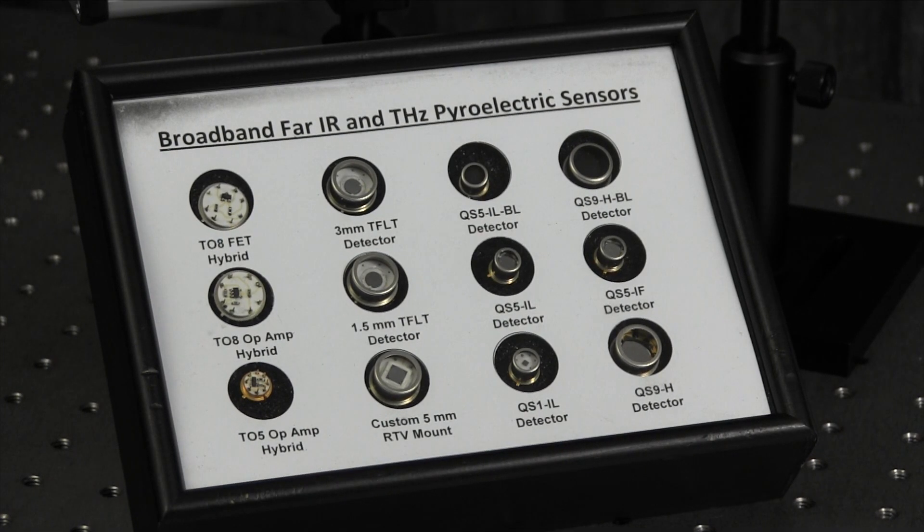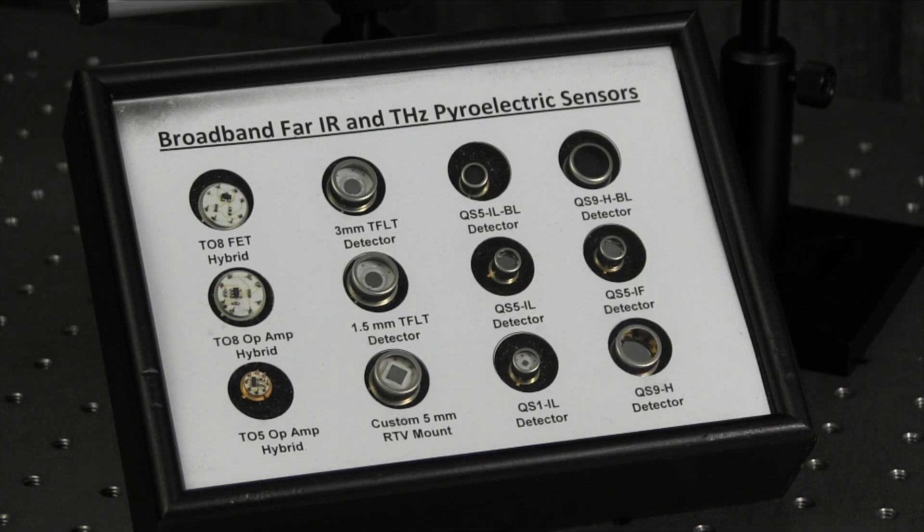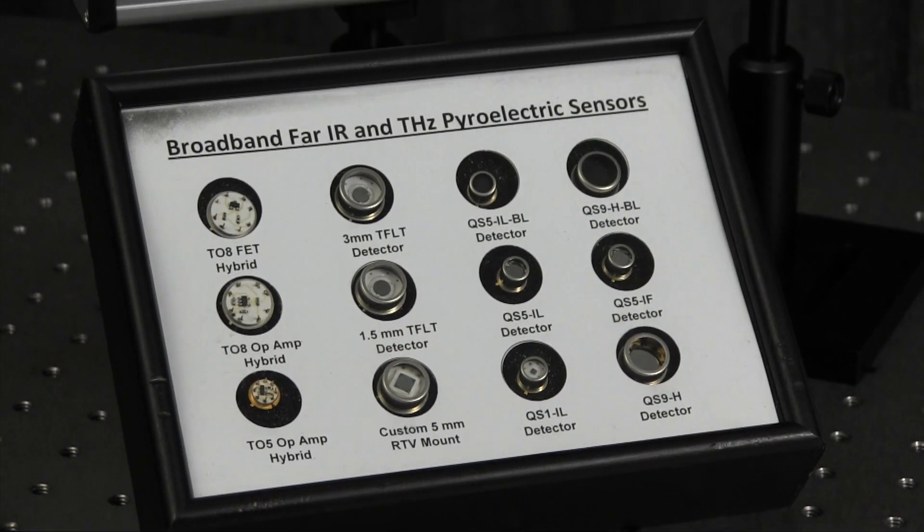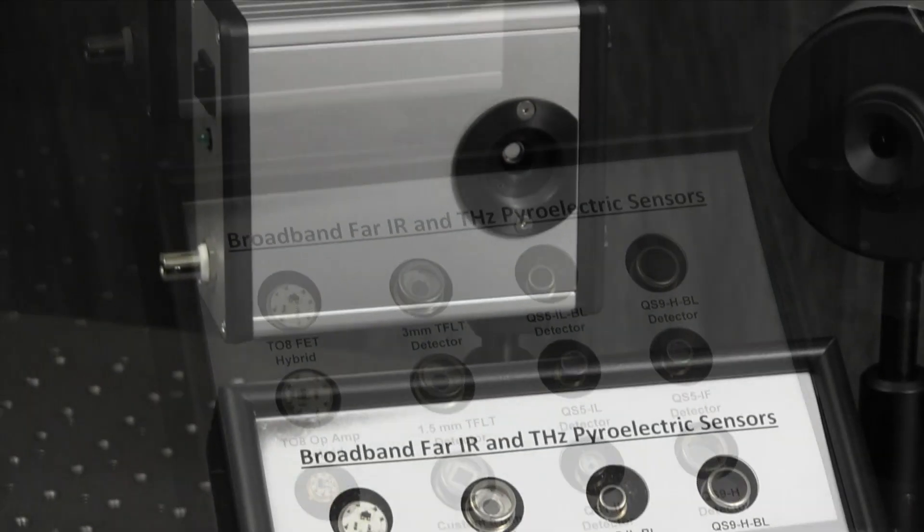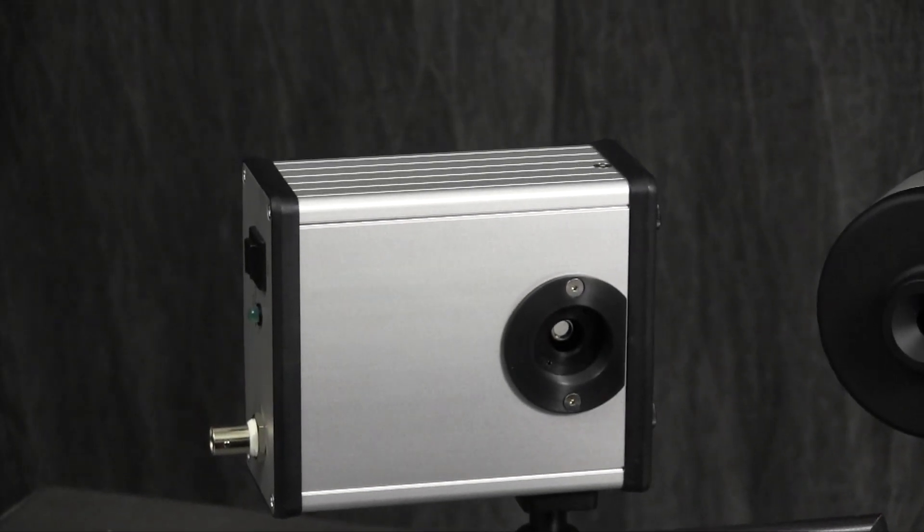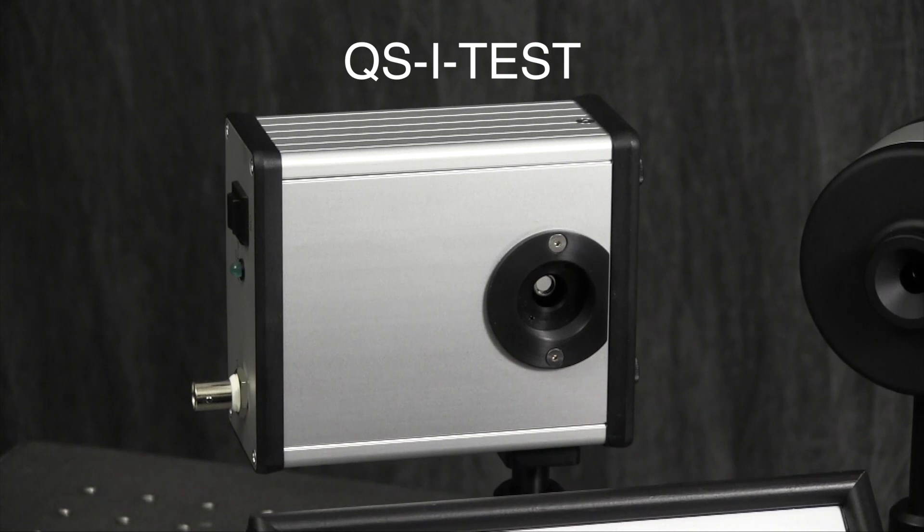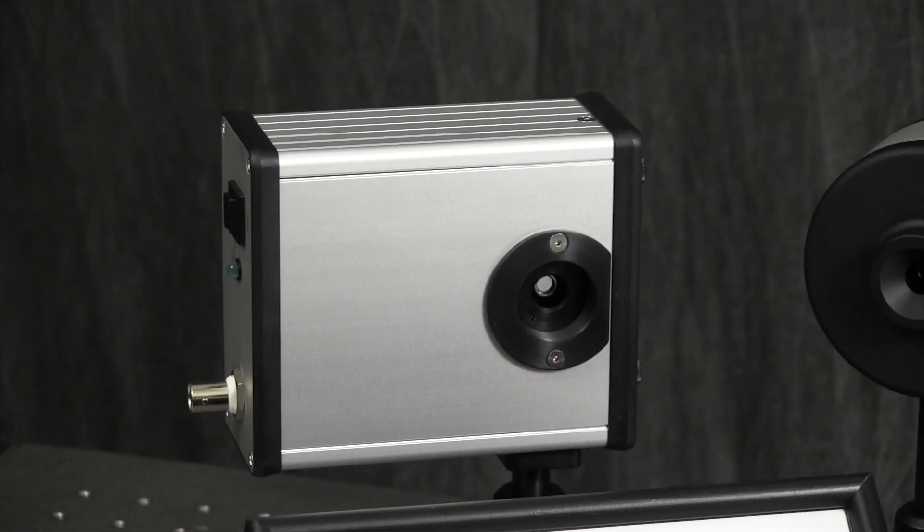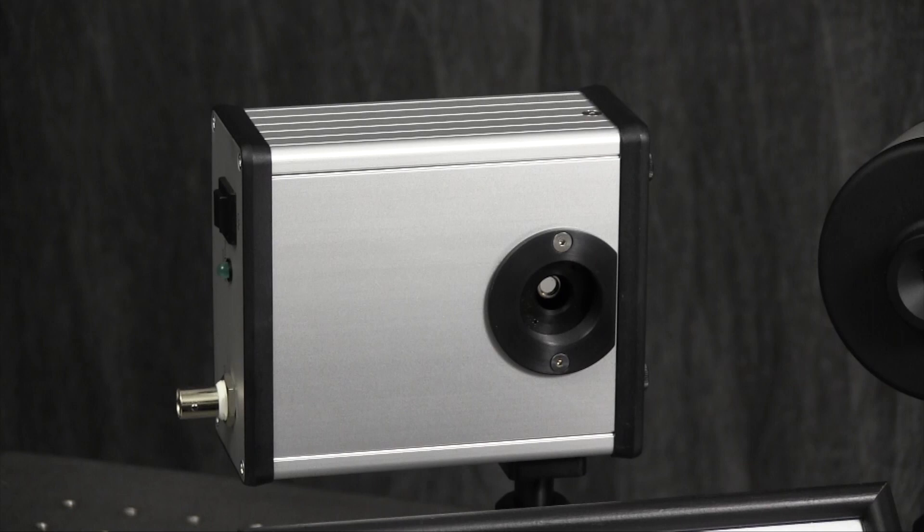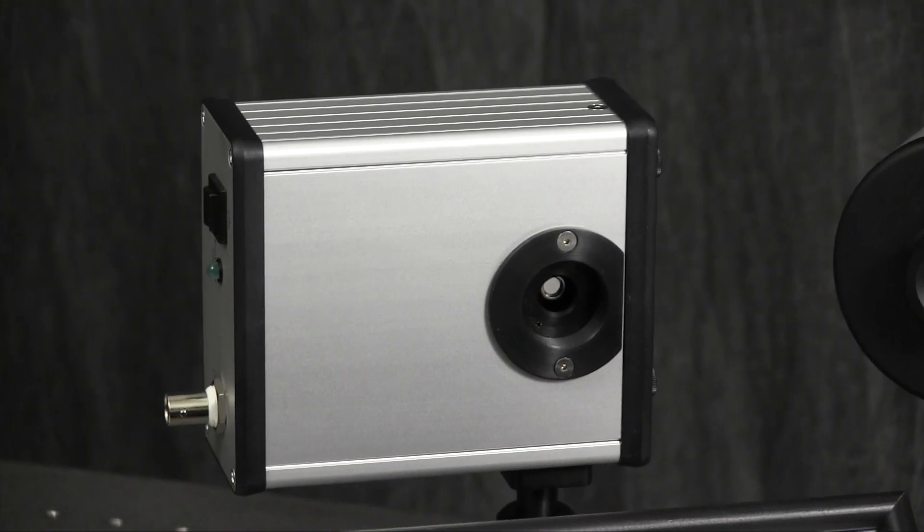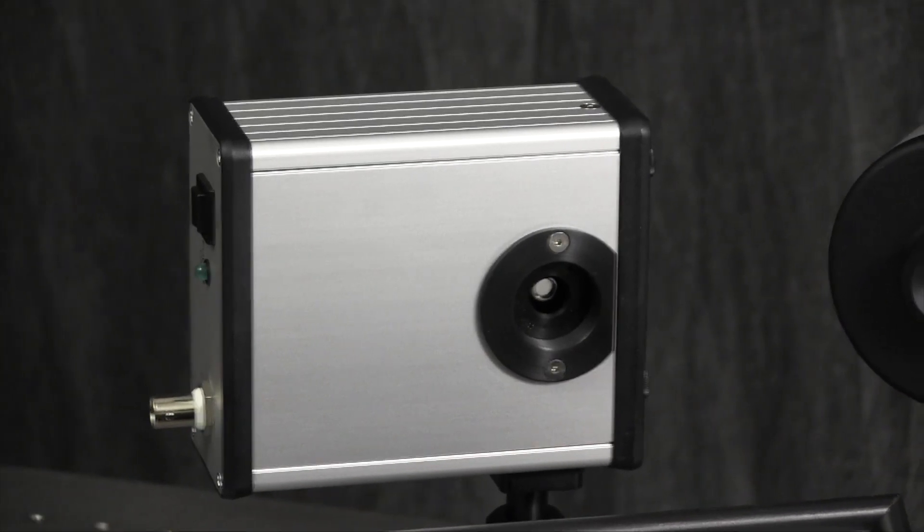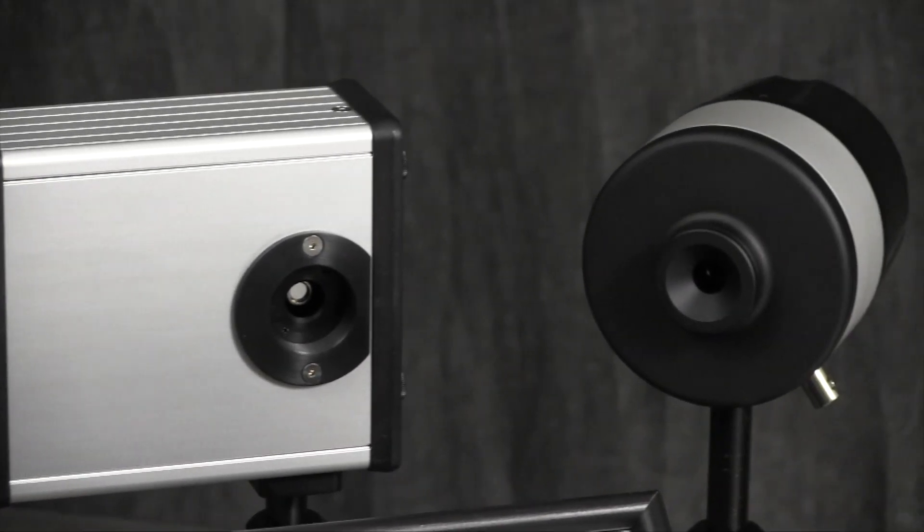They include a carbon black absorbing coating for broad smooth spectral response from 0.25 to 3,000 microns. We designed an evaluation test box, model QSI test, that is compatible with these detectors. Just plug them in. It makes it easy to use the detectors with your oscilloscope or lock-in amplifier to measure the power or energy of your terahertz source.